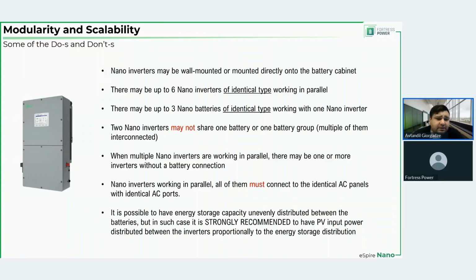Then, it is possible to have energy storage capacity unevenly distributed between the batteries, but in such case, it is strongly recommended to have PV input power distributed between the inverters proportionally to the energy storage distribution. So what does this mean? Let's say you have two nano inverters. One of them has one 60 kilowatt hour battery unit, and the other one has two 40 kilowatt hour units. So one inverter works with 60 kilowatt hours of capacity, and the other inverter works with 80 kilowatt hour capacity, right? So inverter number two, compared to inverter number one, has about 33% more storage to work with. Now then, according to this rule that I just read for you, inverter number two compared to inverter number one must also have 33% more PV power access, right?